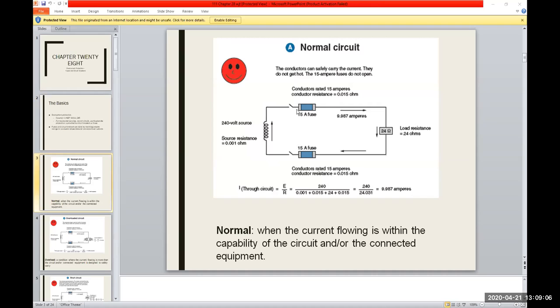You see you've got the two switch points before. If we look at it, there's our coil, the little squiggly line there, where we have our 240 volt source, so two lines of 120 apiece going down. Your first disconnect is probably the circuit breaker there, and then going into the fuse and bringing it back around. And this is just a straight Ohm's law deal. If you look at the formula on the very bottom, where I is the current, the current through the circuit is equal to E over R. In this case, we only have 24 ohms as a load, so that would be the R, and the E in this case is 240.